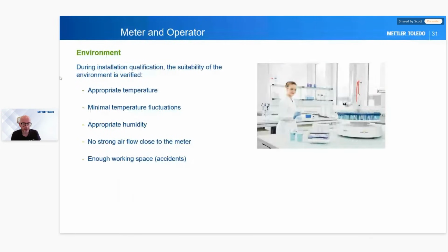When we buy a pH meter, whether we've got one in the lab now or we're going to buy a new one, hopefully, the first thing we need to do is make sure that we put it in the correct place. When we're using it in the lab, we need to make sure that the meter and the system itself are at an appropriate temperature. We minimize any temperature fluctuations. It's at appropriate humidity. We've got no strong airflow. And a really important one is that we've got enough working space.